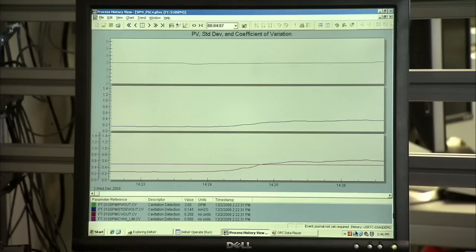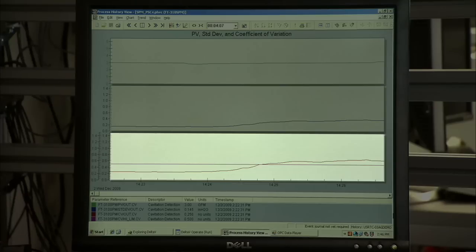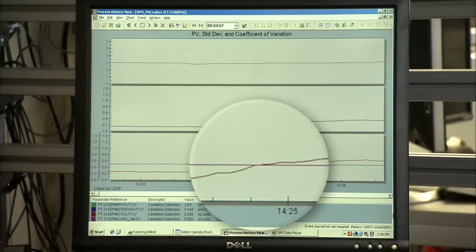Using a data historian, you can see that in addition to measuring the pressure, the 3051S is also measuring the amount of process noise created by the pump. When cavitation occurs, the standard deviation calculated by SPM increases and surpasses the configured threshold.